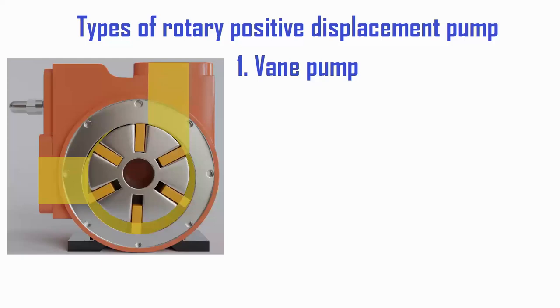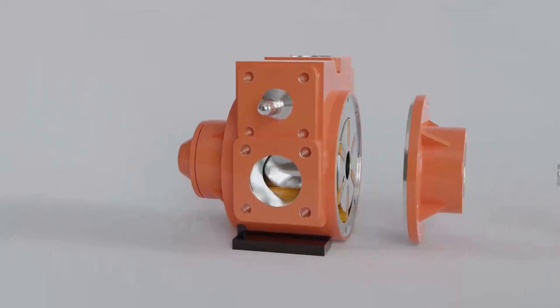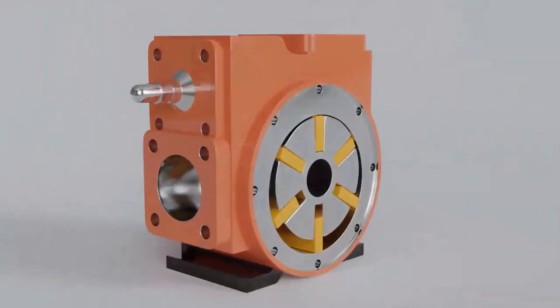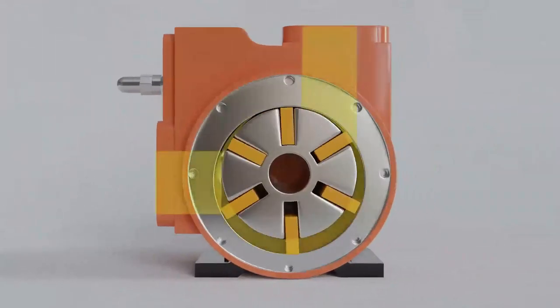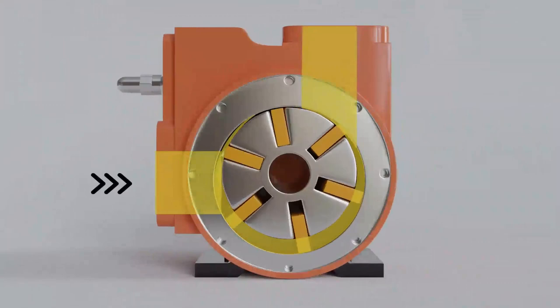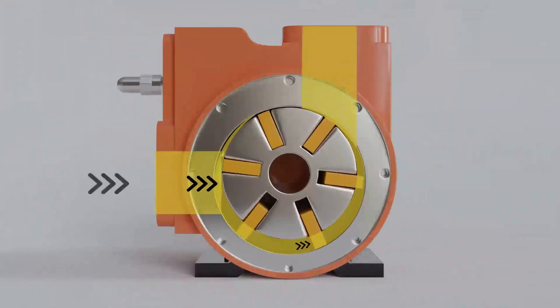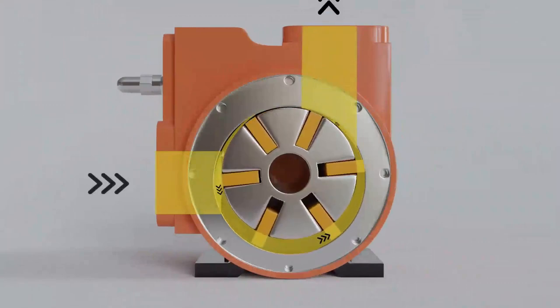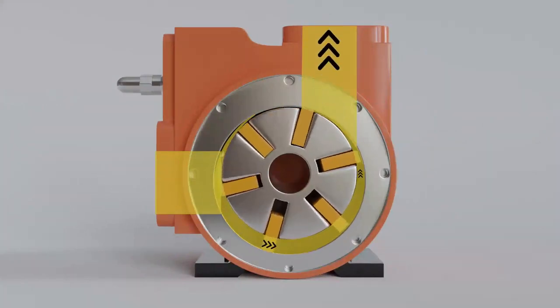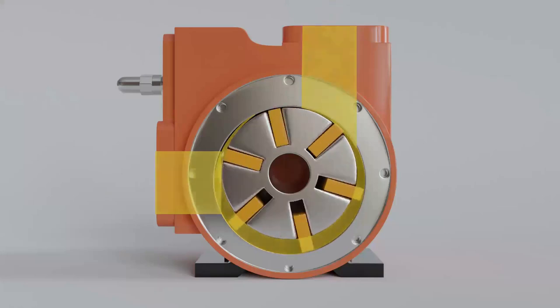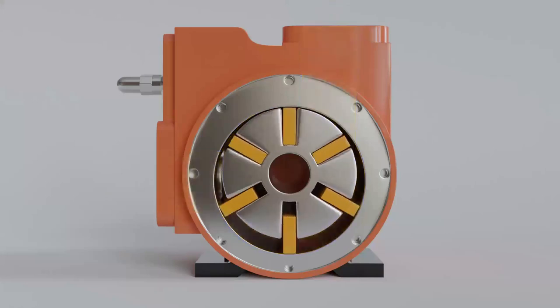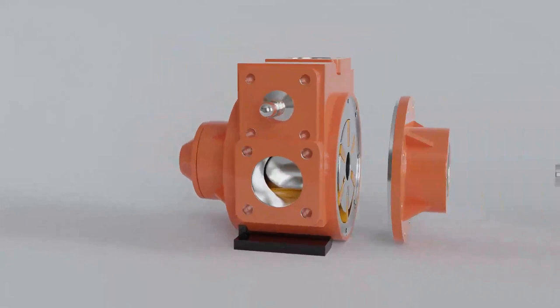The first type is the rotary vane pump. A rotary vane pump is a pump in which the vane in the rotor groove is in contact with the pump casing, and the sucked fluid is pressed from the fluid inlet side to the fluid discharge side while the vanes rotate in the crescent cavity.